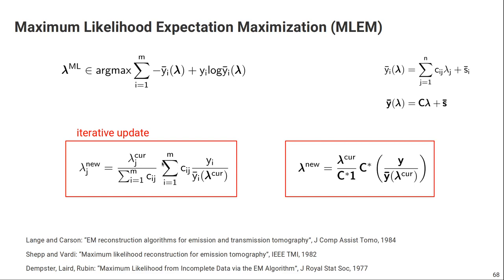Instead of writing the update formula with all the sums — which are necessary to write out the matrix-vector products for the forward model and the backward steps — we can use vector and operator notation. I define the system matrix as an operator C, and say that my vector of expected measurements is the operator C applied to the vector lambda plus the vector of contaminations. Using that notation, I can rewrite the MLEM updates in operator notation: we have a pointwise division of two vectors, then apply the adjoint of the system matrix to a vector of ones, and finally update our image.